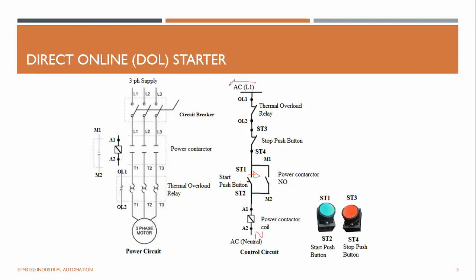So this is L1. You can wire this to any phase, maybe L1 here, and this one to a neutral from the three-phase supply, right? So this is how you do the wiring. Once you press this one, this is closed, and A1, A2 are energized, which means these contacts will close, and the power will flow to the motor. At the same time, when the A1, A2 coil is energized, M1, M2 get energized, and this contact will close. So this is M1, M2, the same M1, M2 here.